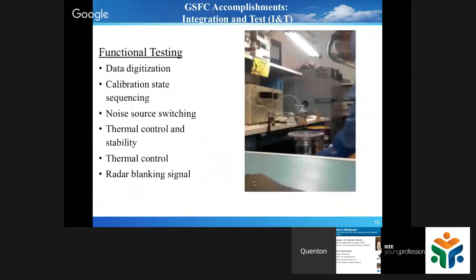After we validate the performance of the instrument, you can see me in the bottom right-hand corner boxing the instrument up to take it to sunny Melbourne, Florida, to integrate it with the radar at Harris. The radar is the silver box standing vertical, and we integrate it with the radar and do interference testing, because the radar can actually damage the radiometer. I think the radar is transmitting about 5 watts, but the radiometer is expecting to see signals on the order of 10 to the negative 16 watts and below.